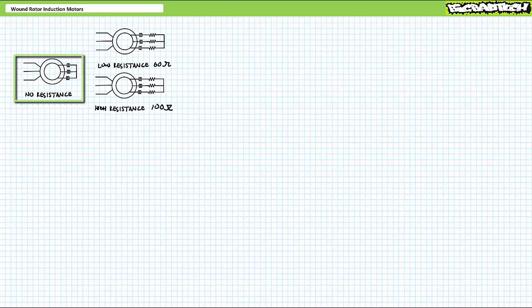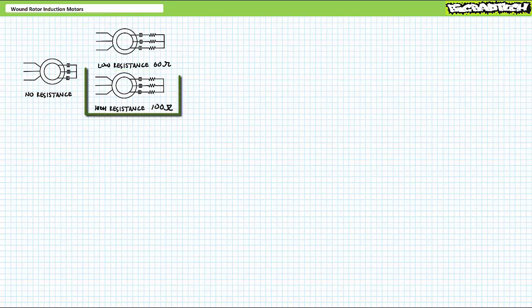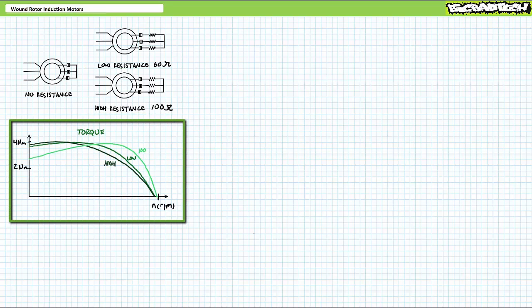For the no resistance configuration, I simply tied the rotor terminals together like the central node of a Y configuration. For the low resistance configuration, I added 60 ohms to each rotor winding in a Y configuration. And finally, for the high resistance configuration, I added 100 ohms to each rotor winding in a Y configuration. Let's compare the speed-torque curves for these three different levels of rotor resistance.